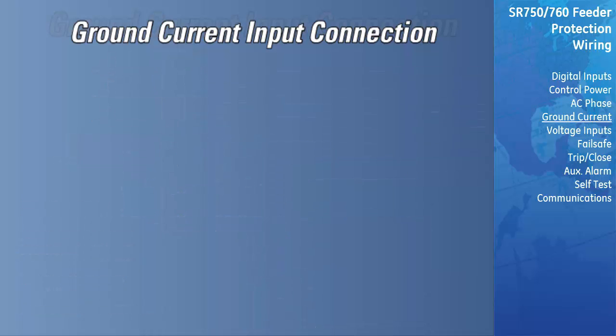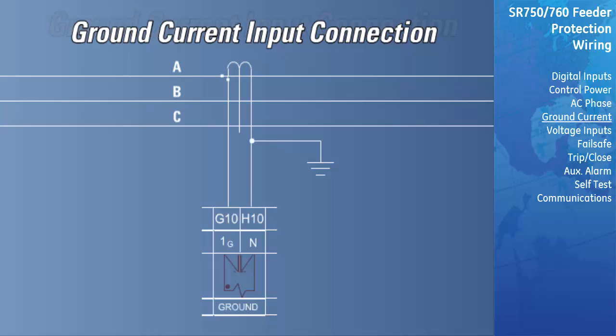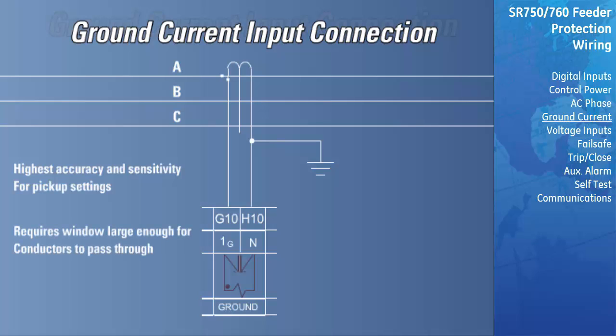The third method is to use a zero-sequence CT. This provides the most accurate ground protection and allows more sensitive pickup levels for ground overcurrent protection. A CT must be chosen that allows all three conductors to pass through the window. The exact placement of a zero-sequence CT so that only ground fault current will be detected is shown here. If the core balance CT is placed over shielded cable, capacitive coupling of phase current into the cable shield may be detected as ground current unless the shield wire is also passed through the CT window. Twisted pair cabling on the zero-sequence CT is recommended.